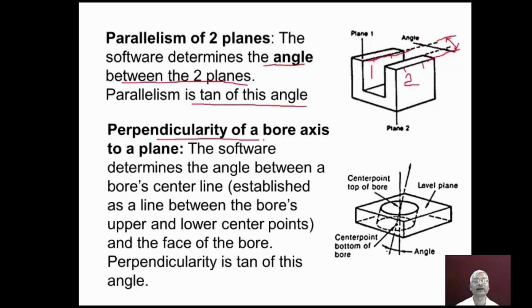And then perpendicularity of a bore axis to a plane. I can see we have a workpiece here with a bore, and this is the bore surface. The software determines the angle between a bore's center line. So this is the bore's center line, established as a line between the bore's upper and lower center points. So this is the bore's upper point and this is the bore's lower center point, and it establishes an axis passing through these 2 center points. That will be the bore's axis.